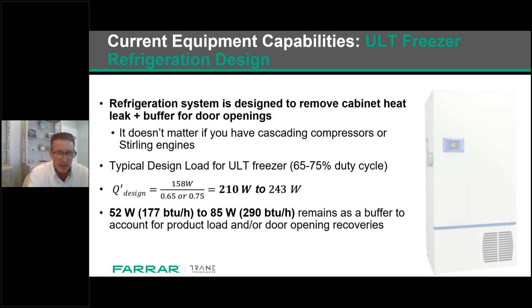Well, this is a relatively small number, between 52 and 85 watts, sometimes referred to as the reserve capacity, which drives the door recovery time and time to freeze as you are placing a warm product inside the freezer, right? So if you take the number that was listed before, 158, less the 243, that's where you end up with the 85 and the 52. Next slide, please.